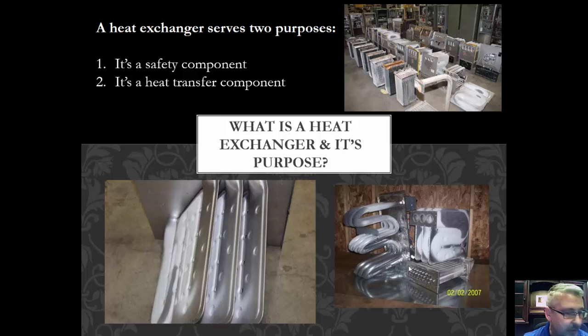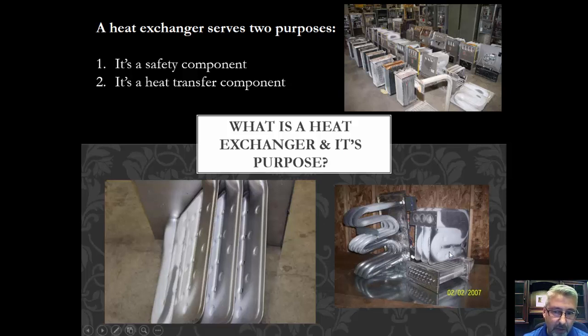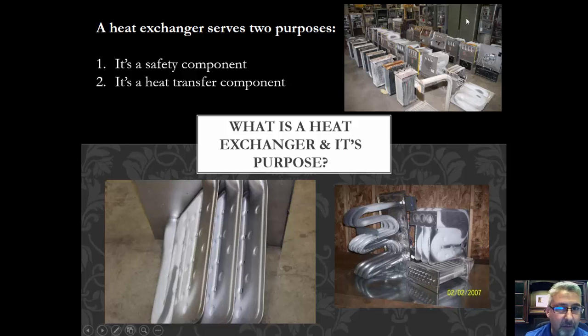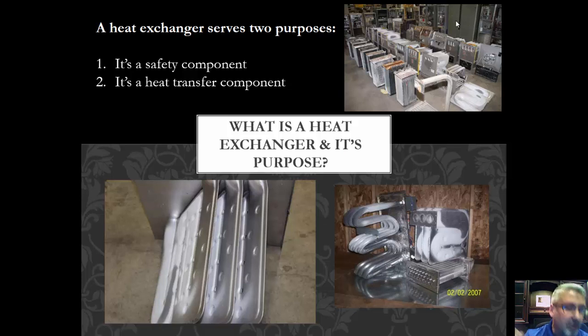You're buying gas, oil, or propane — whatever fuel you're burning — you want to transfer the heated energy through this metal. Down here you'd have a blower. Most furnaces today are timed and have a time delay relay, fan timer board, or fan timer technology built into the circuit board. After so long, it automatically turns on the blower system and you start to transfer that heat to the airspace. Years ago, furnaces like this old Milwaukee Thermal Flow used a bimetal fan and limit control — a little Curly-Q bimetal — that would heat up, turn on a fan, and blow heat across the heat exchanger.